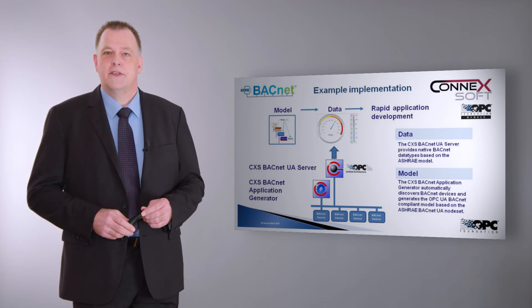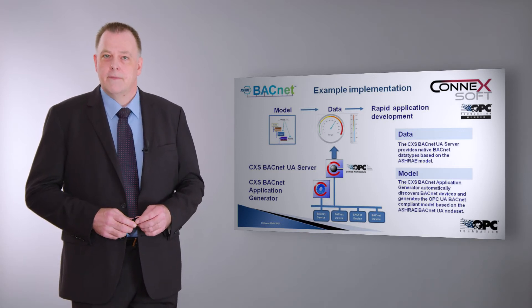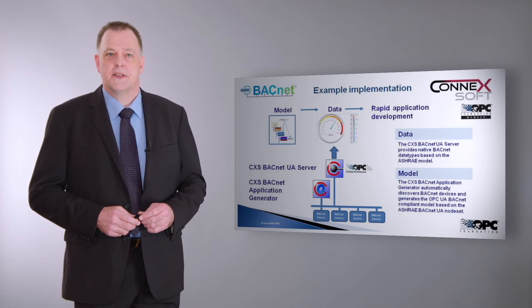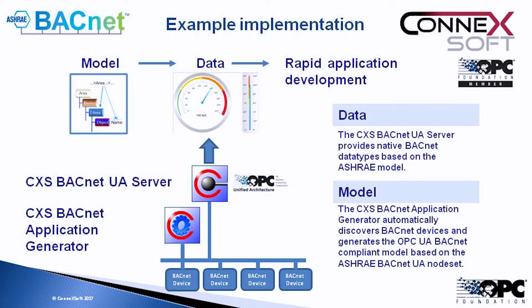We have already received information that companies have implemented this mapping and information model. The company Connectsoft from Munich sent us a presentation, and this overview shows how a typical gateway implementation may look like when implementing the information model. BACnet devices are connected to a gateway which acts as a BACnet client in the middle, presenting this data to OPC UA following the specification in the information model. This may then be presented to enterprise systems for data monitoring, analysis, or event and alarm processing.